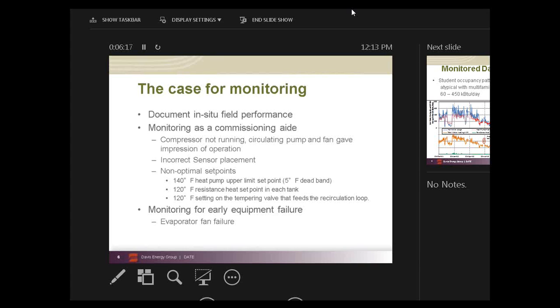About 8 months into monitoring, a bearing in the evaporator fan failed, and the unit shut off, defaulting to electric resistance heat. This failure, again, would not have been noticed for a while, at least not until the electric bills were received. But since we were actively monitoring, we reported the failure, and it was repaired quickly. This failure is likely unique and not indicative of typical unit reliability, but it's worth noting that there was not at any time any sort of feedback that would allow the building maintenance staff to recognize that the unit had failed. So later on, the manufacturer installed a service warning light on the panel, and personnel began doing daily inspections.